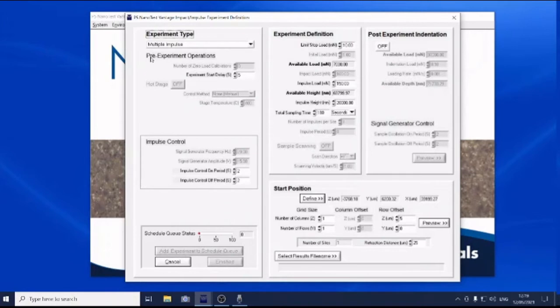And what we're doing is continuously monitoring the depth of the probe as those repetitive impact events take place. So we can define various important elements of our test. We won't go through everything in detail now, but probably the most important element is the load that we're going to use. We already know a little bit about this sample, and we know that 1,500 millinewtons, 1.5 newtons, should lead us to some quite nice failure events. Another important thing is how long we're in contact with the sample surface and how long the probe is out of contact with the sample surface. And we define that using this impulse control on and impulse control off period.